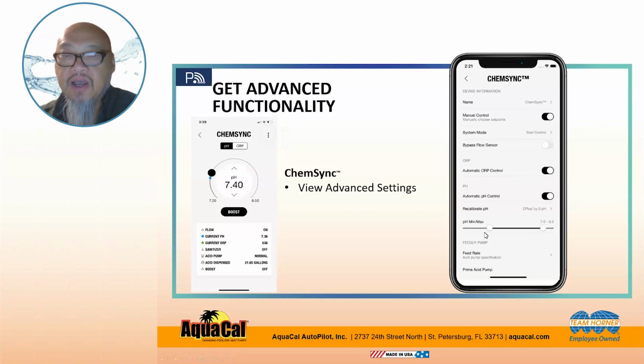pH min and max. We're telling it the acceptable minimum pH and acceptable maximum pH before it gives you a warning. The normal factory setting is between 7.0 and 8.0. If we start seeing that pH rise above 8.0, it'll give you a notification, a warning to let you know that there's something wrong. Either the probe is dirty, or it could be that the acid tank is void of any solution.